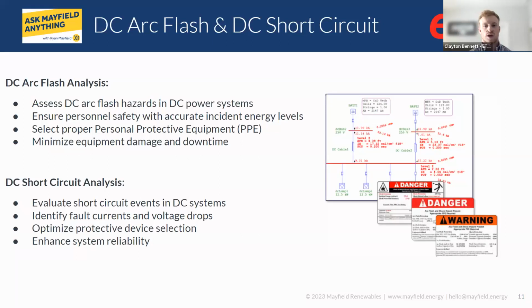And as we discussed, while all of these are NFPA 70E compliant, these help determine PPE for workers. And ETAP does a really good job of providing options for any kind of label you would need, specifically here to produce DC labels. We can also use these methods in ETAP to determine fault clearing time from DC protective devices. You can also model any sort of PV, batteries, chargers, UPS, DC motors, and AC-DC converters, among other inverter-based resources.